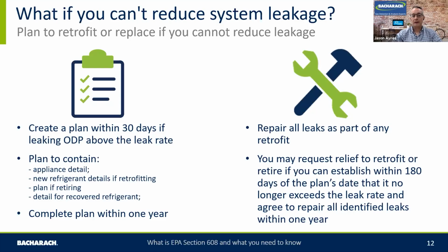If you're going to retrofit the equipment, so take out the original gas and replace it with a new gas, and as part of that, I'm sure it's that journey to reduce to a lower GWP refrigerant, you also need to make sure that you repair all the leaks on that system at the same time as replacing that refrigerant. So it's not just a refrigerant change, it's also doing all those good things to ensure that the refrigerant doesn't leak out afterwards. There are options to request relief to the retrofit or retirement program within a 180-day window, which could then mitigate you actually having to enact that plan.